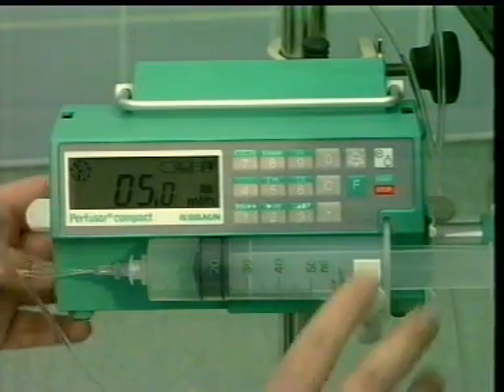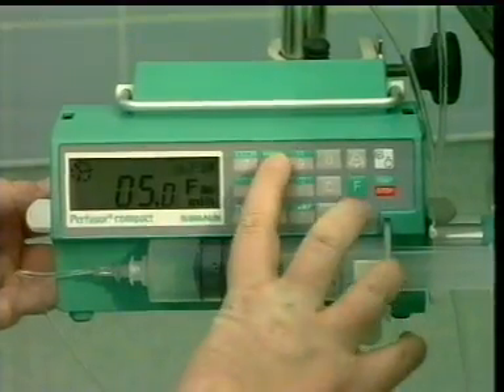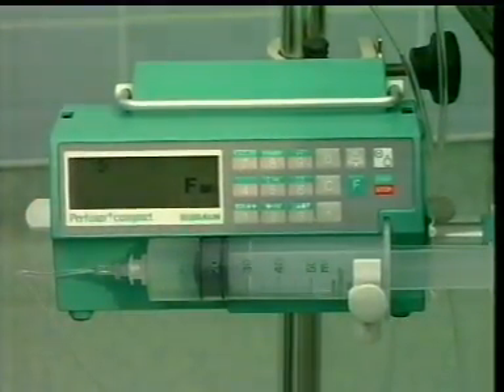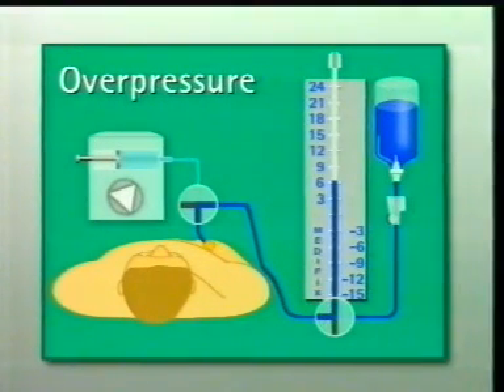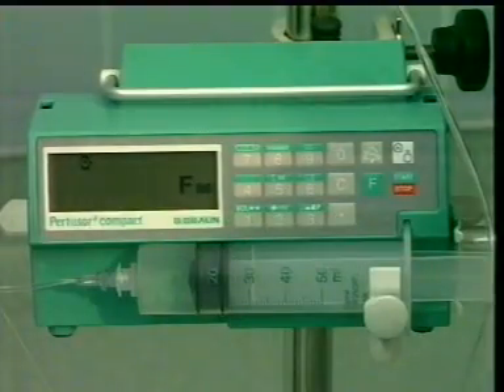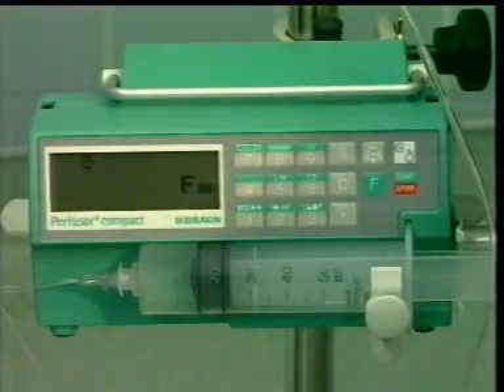If one neglects to switch off the infusion pump during the measurement process, then there's a risk of later administering a bolus infusion. In the infusion tube, which is closed during the measurement process, pressure builds up. If the alarm limits of the infusion pump are not correctly set, then this excess pressure may remain undetected. When the three-way stopcock is opened following the venous pressure measurement, the patient receives a large multiple of the intended infusion dosage in a short amount of time. The risk is obvious. It is therefore important to proceed carefully with interruption of the infusion.